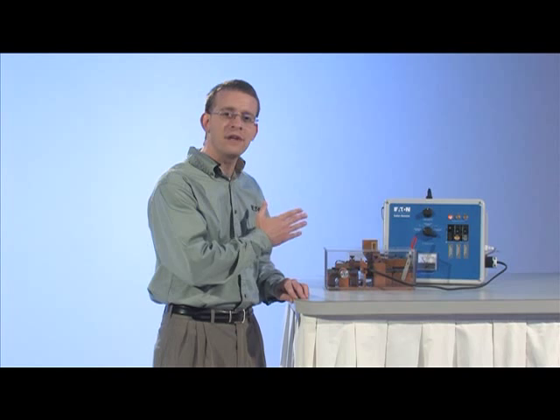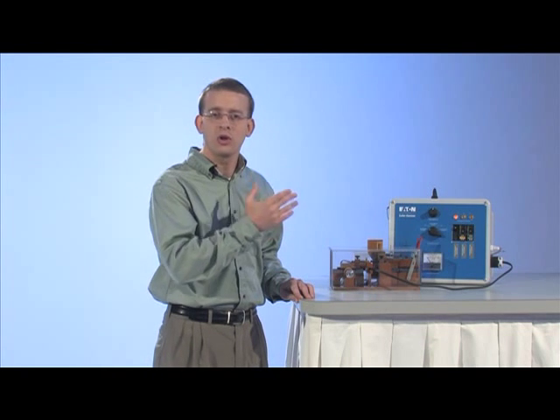Now the device I have here is designed to recreate this high current arcing fault on a circuit monitored by a typical thermal magnetic breaker. If I cut into the lamp cord quickly, it will create a short circuit, which this breaker will obviously detect. But the conditions leading to a high current arc are much more subtle, not nearly as abrupt as a short circuit.